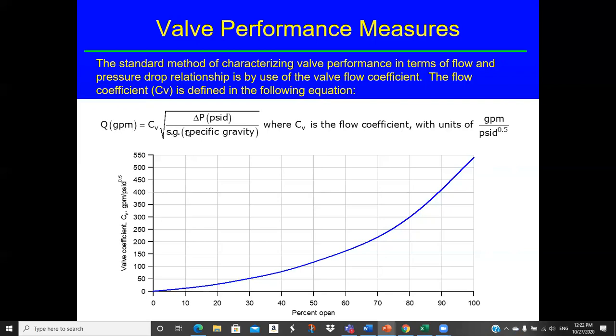Now, there is also a geometry factor that can be included with this. And we'll talk more about this. If the geometry factor is 1, that would indicate that the upstream pipe, the valve itself, and the downstream pipe are all the same diameter, okay? And if not, then there is a geometry factor, I think it's an F sub P, that we can calculate to put in here. If you download the PSAT program, I'm hoping that it's still available. It comes with a valve tool, which is very, very handy. And I'll show some screens and probably demo that some today. If not today, then in the next class.